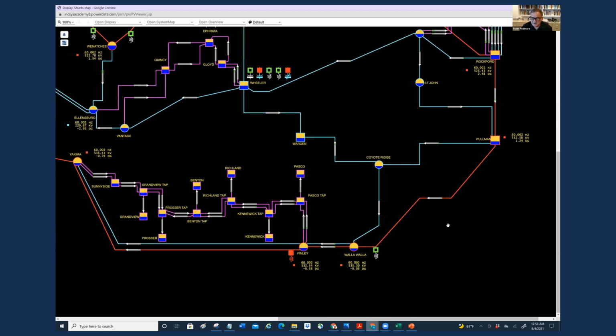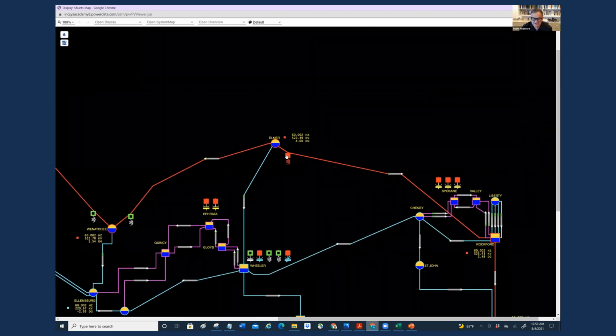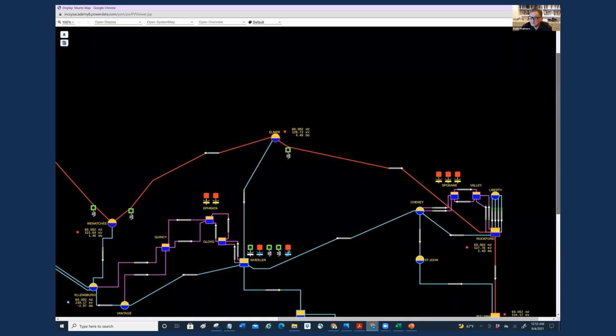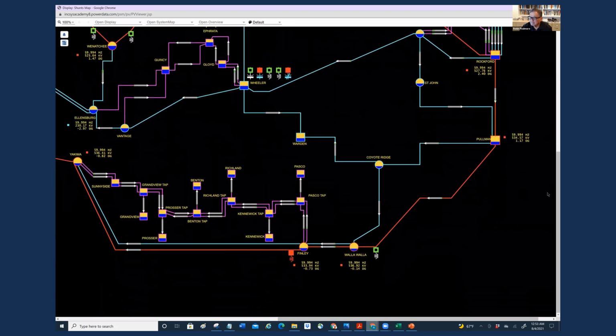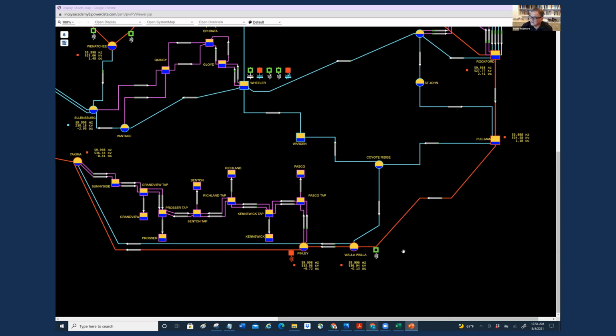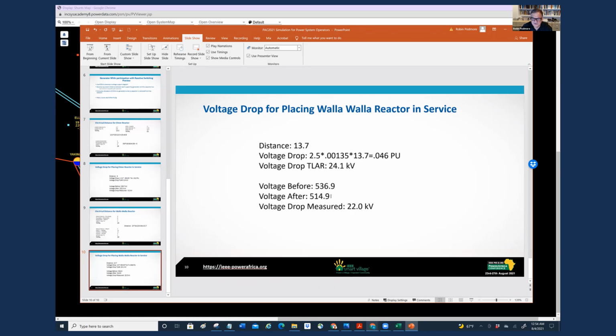Let's come on to the other side of the system at Walla Walla. And before we do that switching, we'll take this reactor off. In this case, we're starting with 536.9 kV, and we put the reactor in service, 250 megavars, and we drop all the way down to 514.9. So that's the summary here, 536.9 all the way down to 514.9 for a 22 kV drop. And the TLAR estimate we got from a distance of 13.7, and then with 250 megavars, which is 2.5 per unit, we're predicting 24.1. And again, given the complexity of the system, that is a very good estimate.